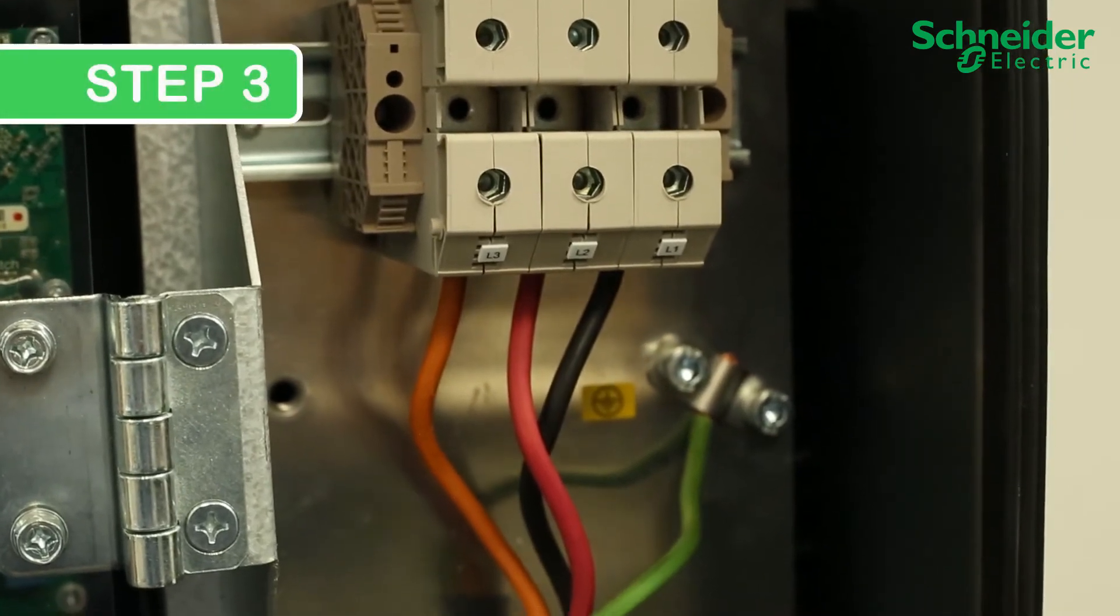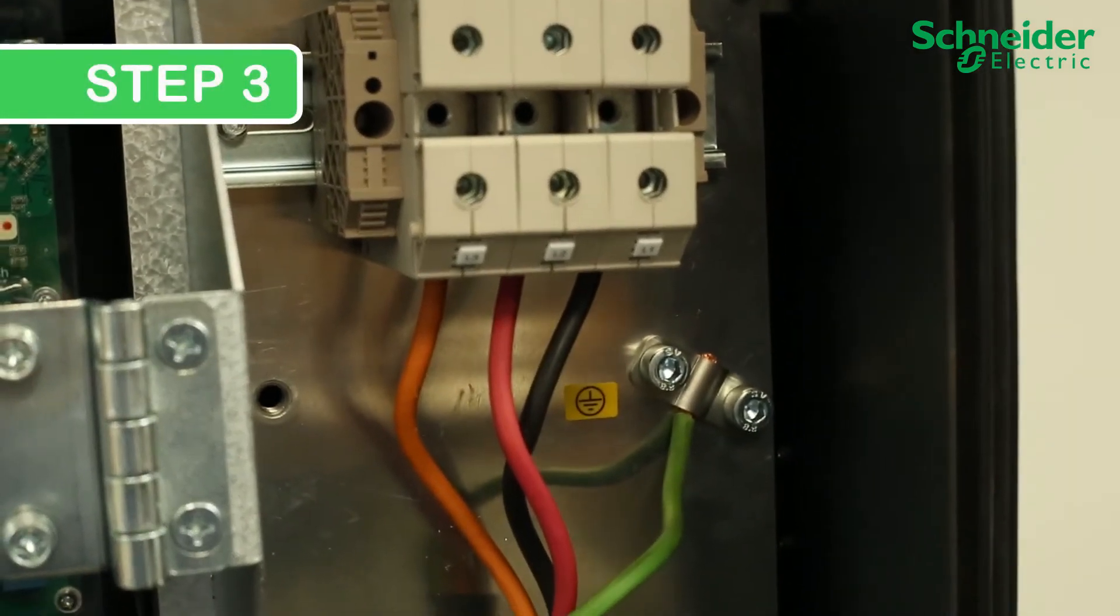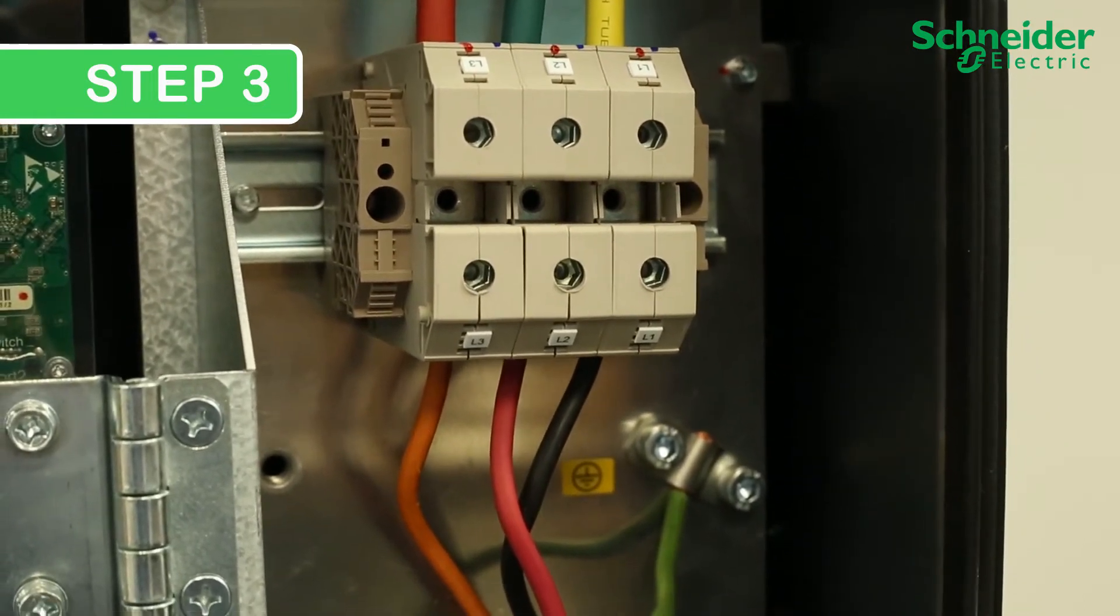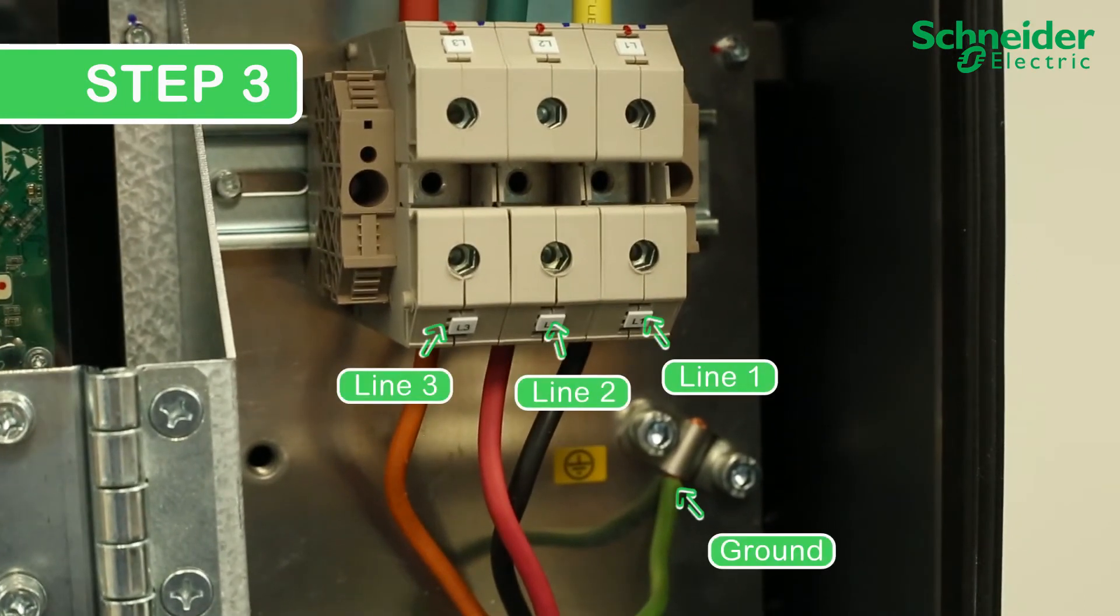Installation methodology of the AC conductors in the CL60A is similar to the CL60E with a few notable differences in configuration: three hot phases, no neutral, and the ground going directly to the mounting plate for the AC terminal block.